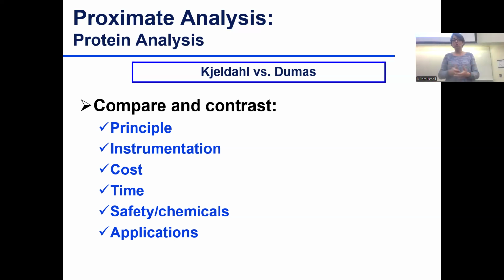The only thing you do is weigh the sample and then put it in the carousel. It might seem very simple to you, but there's a lot of work that the analysts do by calibration, making sure the system is maintained, cleaned. It's a very high maintenance equipment. But if it's functioning really well, then you can analyze a lot of samples in a short period of time.